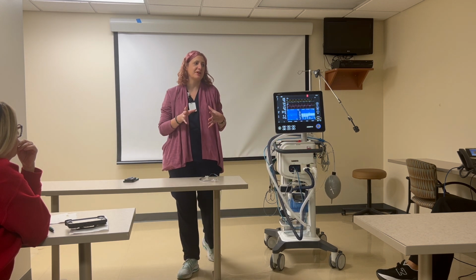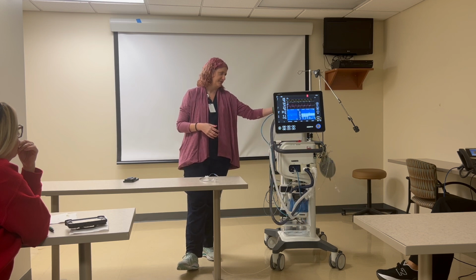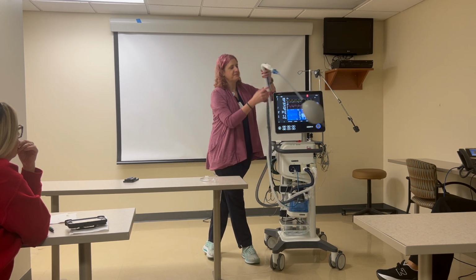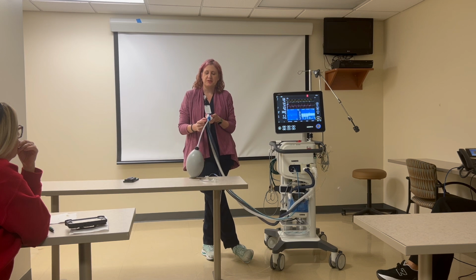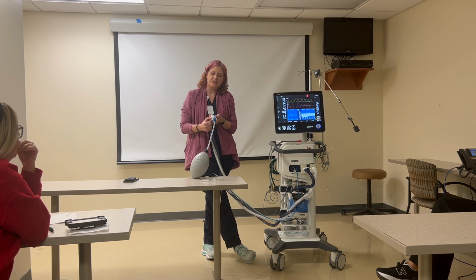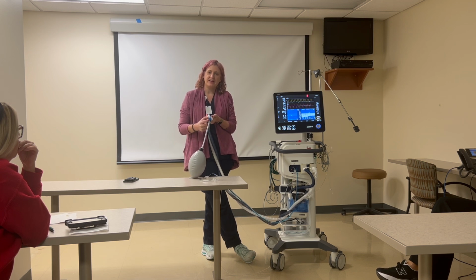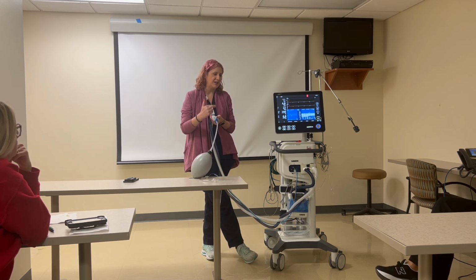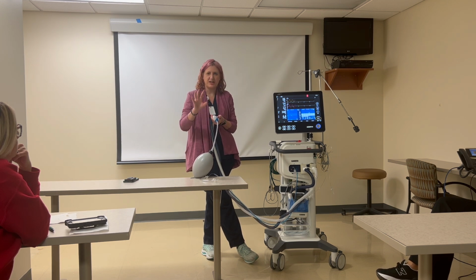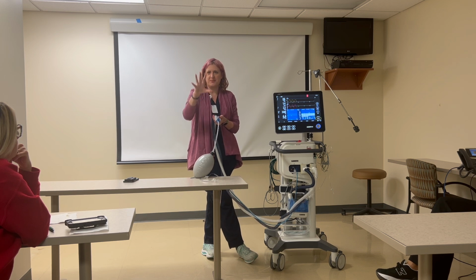But what can happen if you were getting that patient to swallow, or if they were coughing too fast, breathing too fast, with the way that they're breathing, because we have a flow sensor at the end, it's doing all the measurements here. So if that patient is coughing and breathing too fast, it can trick the flow sensor into thinking they have a disconnect from the patient right here, when in reality the patient is coughing and inhaling at the same time, and the flow sensor can't predict that. And so that's why that alarm went up, cleared itself, went up again, then cleared itself.